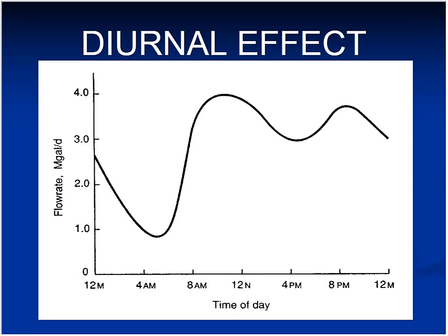What you see here is if you start here at 12 midnight, we've got a flow rate of about 2.6 million gallons, and it just drops off steadily down till about 5 o'clock. Everybody's home and in bed. You've got some 24-hour operations, late night at Taco Bell and that sort of stuff, but not much is going on, so the flow drops off. Then at 5 o'clock, what happens? The alarm goes off. You've got to get up, get the kids ready for school, take a shower. Dunkin' Donuts is backed up into the street and everything else. Well, it goes up dramatically up to midday.